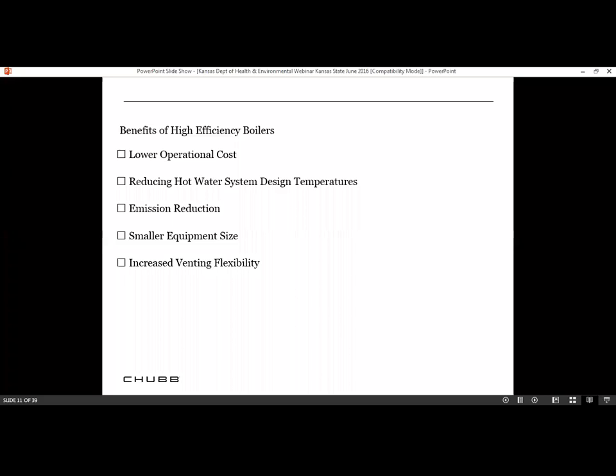If you look at the benefits of these high efficiency boilers, there are lower operational costs. They reduce the hot water system design temperatures. The emissions reductions, the low NOx reductions is very critical. Smaller equipment size. If you look at boilers 100 years ago, they were in schools, for example, some of them were a story and a half tall. Nowadays, you can do the same kind of heating with boilers that are probably 3 foot, 4 foot tall in series, several in series. Smaller equipment size and increased venting flexibility.